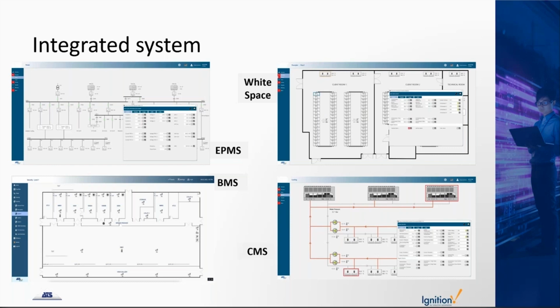What you need is an integrated DCIM system, like the one we are using based on Ignition. If you go to the top right part, you see the white space. In the white space, you see the racks and the temperatures and the humidities and the CRACs. So you have a good idea about your SLA contracts and so on. The left part is your EPMS, so the electrical power monitoring system. You can see your power consumption. The bottom part is your BMS, so you know everything about oil users, diesel users, water users, and so on. And the right bottom part is the CMS, the cooling management system.